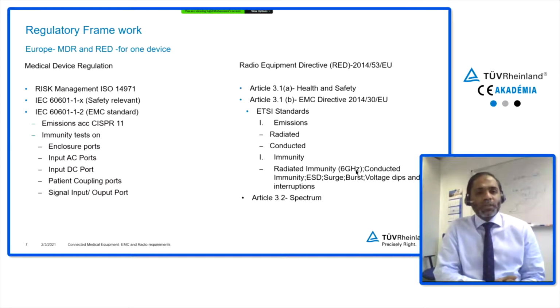Medical device regulation, also called MDR, stems from the risk management standard ISO 14971, and then the relevant IEC 60601-1-X, the safety relevant standards, followed by IEC 60601-1-2, the EMC standard, which we will delve into in much more detail in the next slides. The emissions under 60601-1-2 are according to CISPR 11, and immunity tests are laid down on the enclosure ports, input AC ports, input DC ports, patient coupling ports, signal input and output ports.